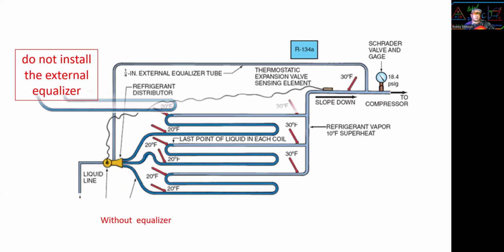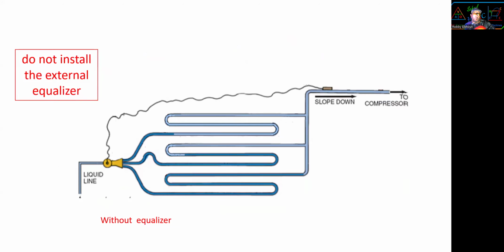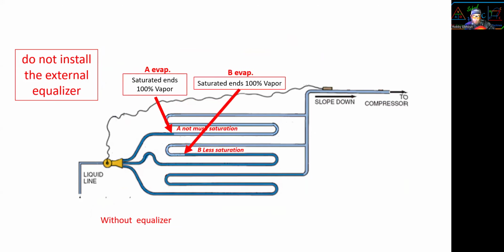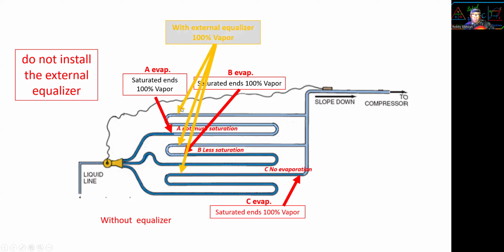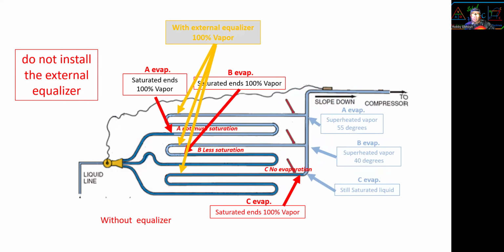All right, now do not install an equalizer. What will happen? No equalizer line. Evaporator 1, there will not be too much saturation. The freon will boil quickly. In evaporator 2 in the middle, saturation will end over here, and the bottom one will be flooded. Saturation ends 100%, barely. Okay, so now with the external equalizer, all 3 are even. Without the equalizer, temperatures and pressures are different in the evaporators. Superheat 55, superheat 40, and here superheat 0. Still saturated liquid.